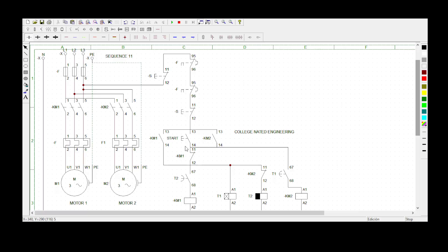Only after 10 seconds can you start Motor 2 using the same start button — you must come and press the start button again. Then 10 seconds after Motor 2 has started rotating, Motor 1 must stop rotating automatically.